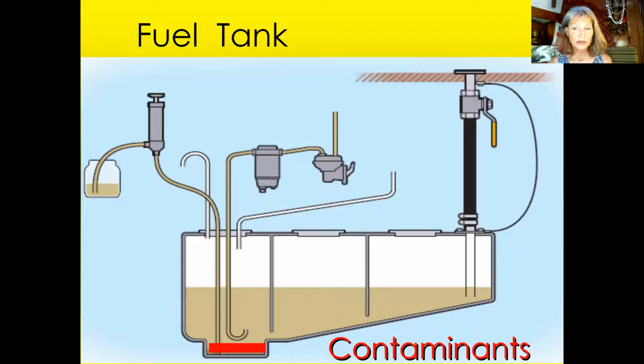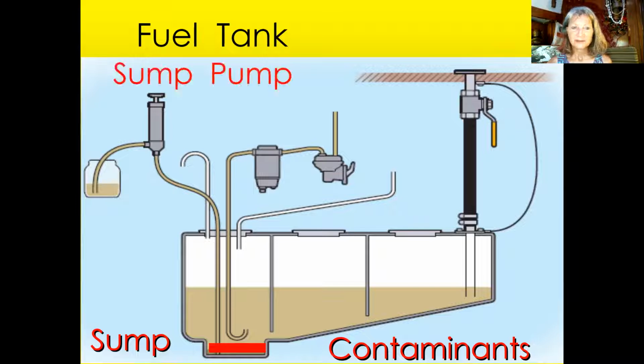You can also install a sump pump yourself. It's basically pumping out by hand anything from the bottom of the tank, because the sediment will settle, and then you can tell the quality of the fuel in your tank. A little brass sump pump sucks out the fuel, puts it into a jar, and you can inspect it and say, hey, is our tank looking good?